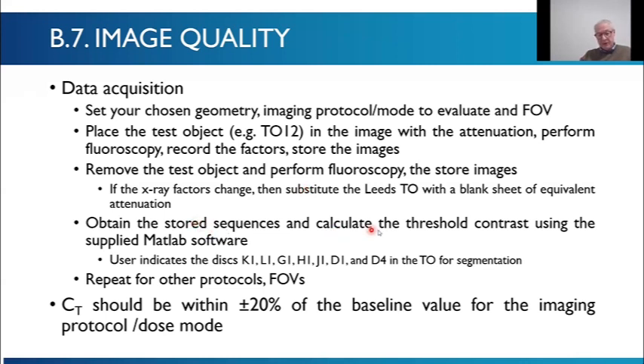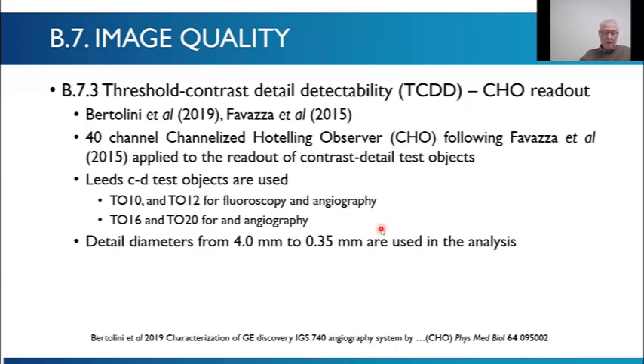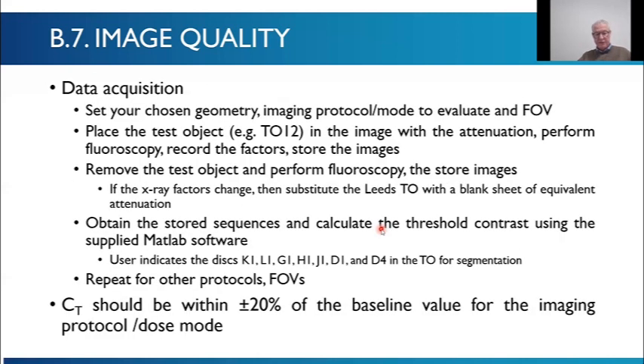Store the sequences. I think you need, I'm going to say here, about 400 images for this. Then you indicate on the test object where your targets are, and the software segments the signal present and signal absent regions and calculates your threshold contrast. For all three methods, this threshold contrast that you evaluate, or signal to noise ratio, should be within plus or minus 20% of the baseline value for your mode.